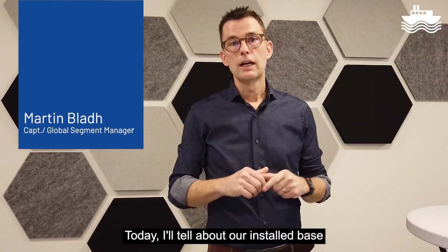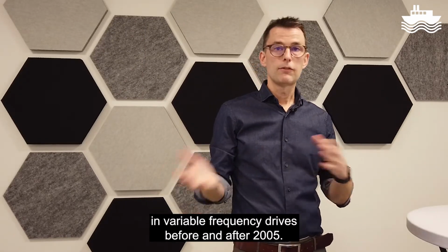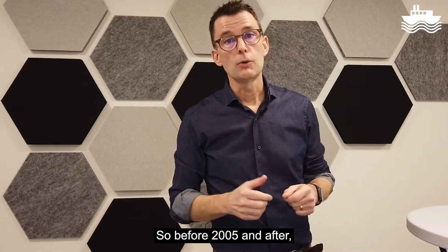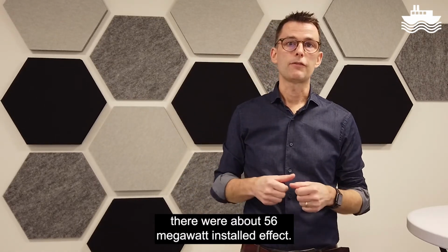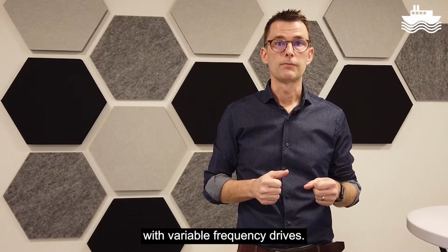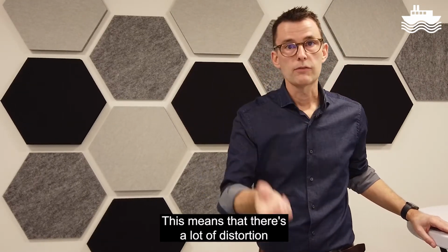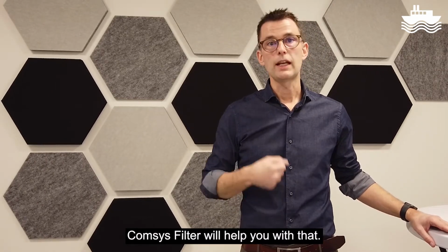Today I'll tell about our installed base and a little bit about a cruise ship and the difference in variable frequency drives before and after 2005. We'll start with that. So before 2005 and after, there were about 56 megawatt installed effect. Before 2005, that was about 10% with variable frequency drives. After 2005, it increased, so now it's about 70%. This means that there's a lot of distortion that has to be handled. Comsys filter will help you with that.